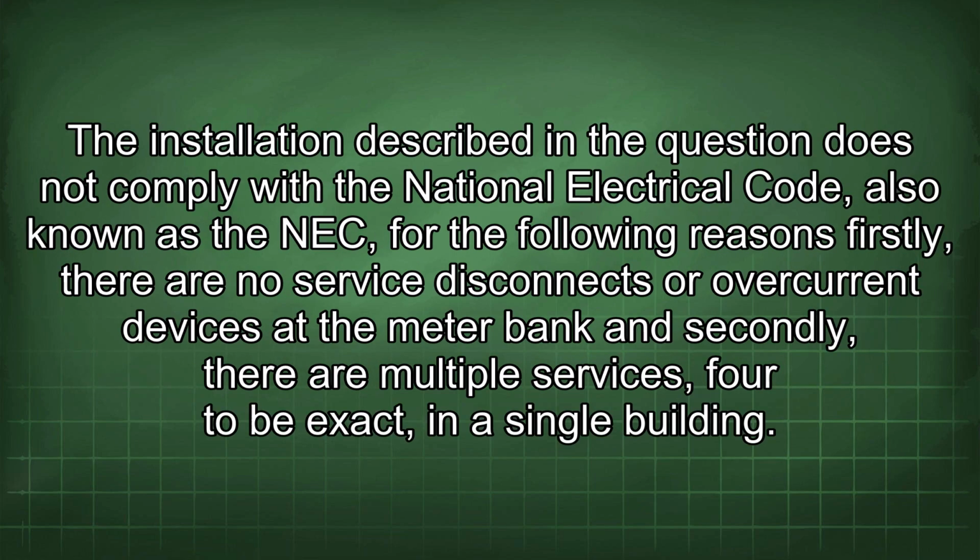The installation described in the question does not comply with the National Electrical Code, also known as the NEC, for the following reasons. Firstly, there are no service disconnects or overcurrent devices at the meter bank, and secondly, there are multiple services, 4 to be exact, in a single building.